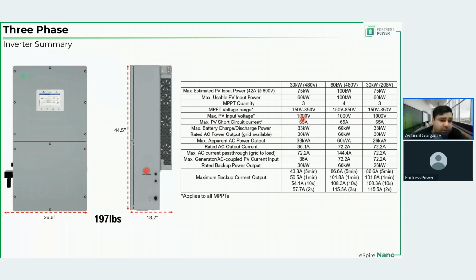So maximum PV input voltage for any of the nano inverters is 1000 volts. The voltage range in which the inverter can actually do maximum power point tracking is 150 volts to 850 volts, which is very impressive if you ask me. MPPT quantity, the 60 kilowatt inverter has 4 of them, as I said, and 30 kilowatt inverters have 3. Each MPPT has 2 positive and 2 negative ports. So you can connect 2 strings per MPPT, provided that those strings are identical in all possible aspects. Short circuit currents, that's why you see such a high number, 65 amps, because that short circuit current must essentially accommodate 2 strings connected in parallel to 1 MPPT.